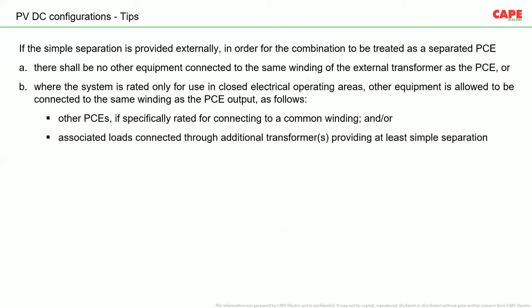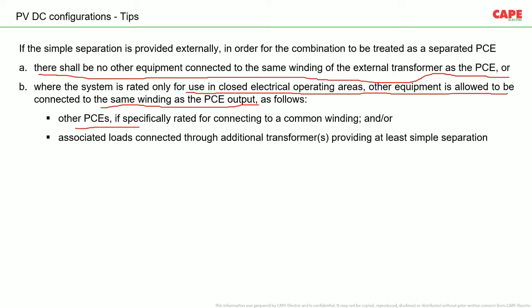Now, if you use a combination of one transformer with many inverters, sometimes people buy inverters without a transformer, and sometimes 5 inverters are connected to one isolation transformer. You should also look into these requirements. There shall be no other equipment connected to the same winding of the external transformer as the PCE. That means you have a dedicated transformer for each PCE, and you shall not connect the secondary winding of the transformer to a load other than the PCE. If the system is rated only for use in closed electrical operating areas, other equipment is allowed to be connected to the same winding of the PCE output as other PCEs, if specially rated for connecting to a common winding.